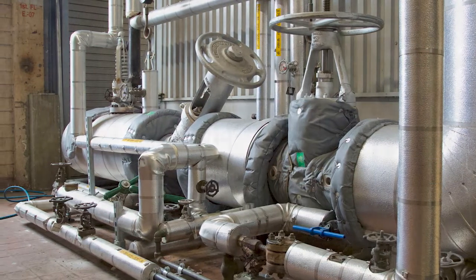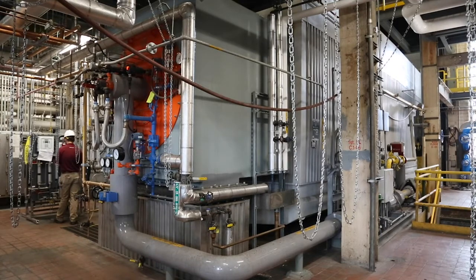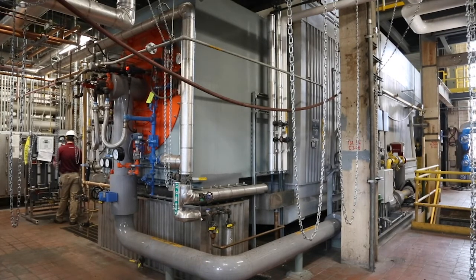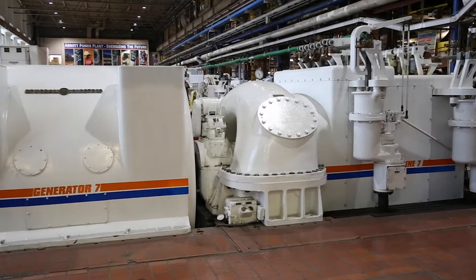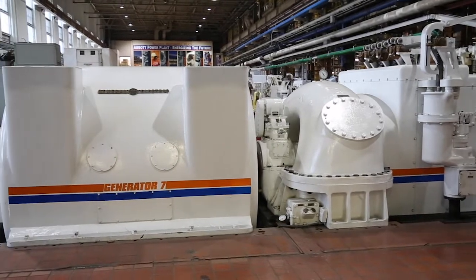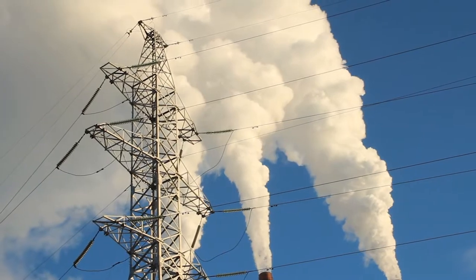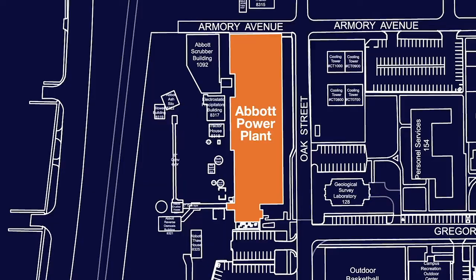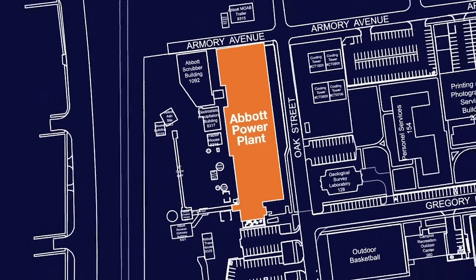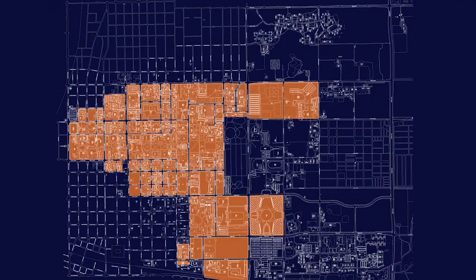The second system consists of water tube boilers powered by natural gas. They can also run on fuel oil if the gas supply is interrupted. The boilers convert water into high-pressure steam, which is fed into a turbine that spins a generator to produce electricity. In a conventional electric plant, all that heat in the steam would be wasted. Here, it's captured and distributed to the campus through a vast network of underground pipes to heat dorms, classrooms, labs, and other buildings.